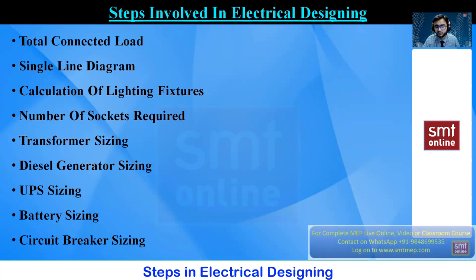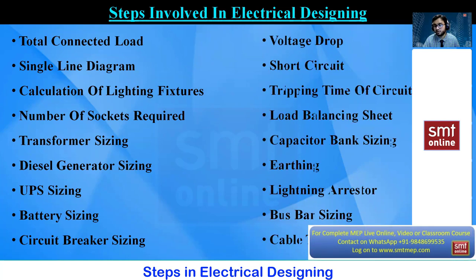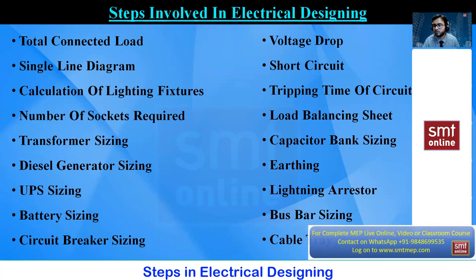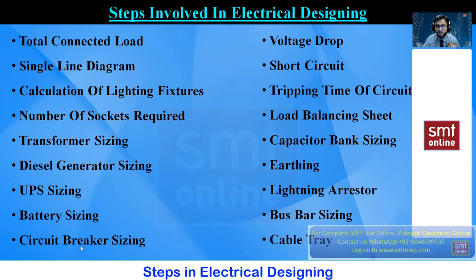Cable sizing is a very vast and detailed calculation area. First we understand the type of conductor required, then select the insulation level, and based on manufacturer data and resistance values we propose the cable. Once proposed, we justify it using voltage drop calculation, short circuit calculation, and tripping time calculation. For example, if you send 230V over 25 meters, you may not receive the same 230V due to internal losses. Short circuits occur due to insulation failures causing excess current. The tripping time determines how quickly the circuit breaker trips for a given fault level.